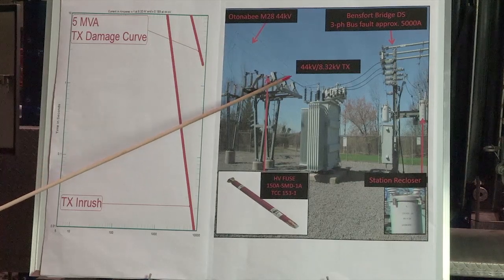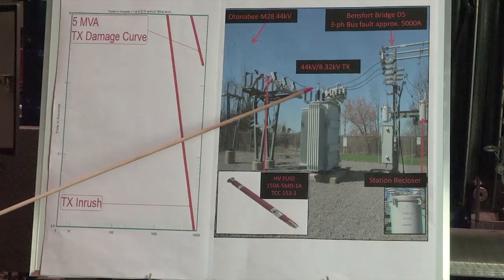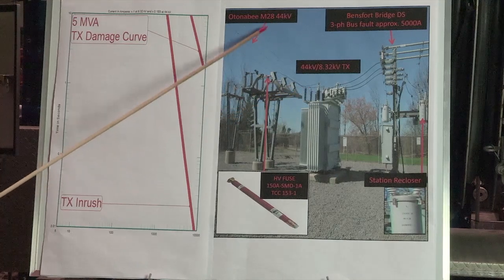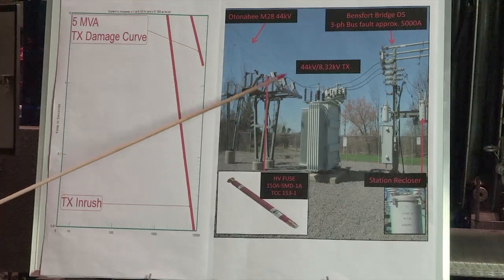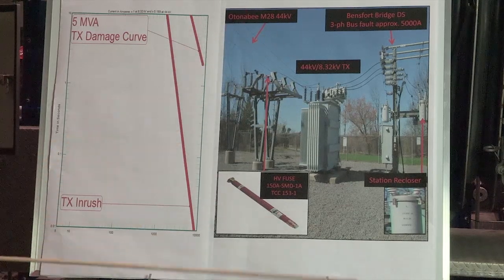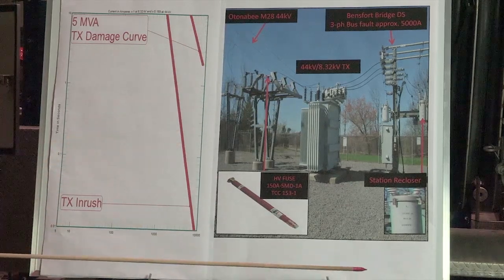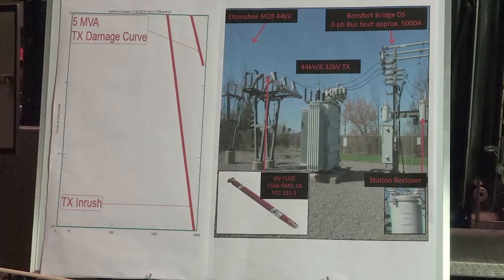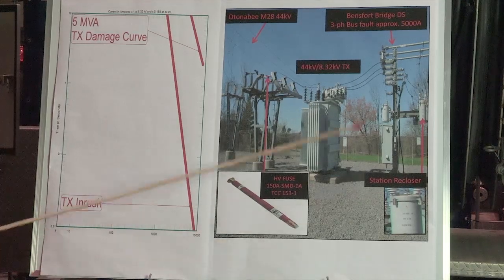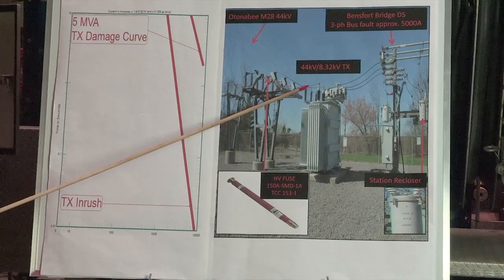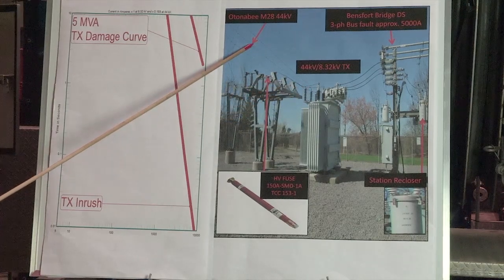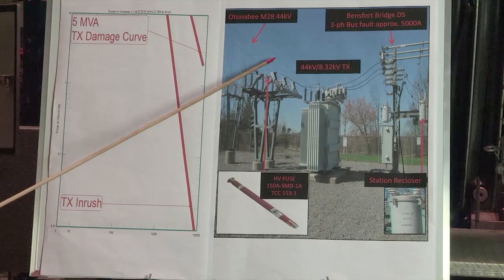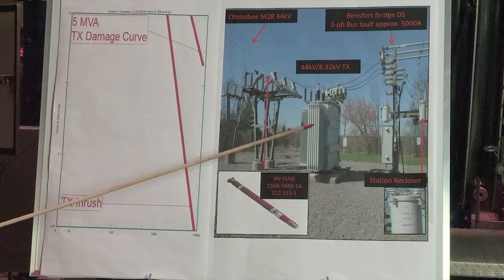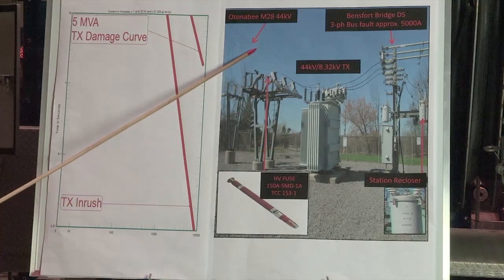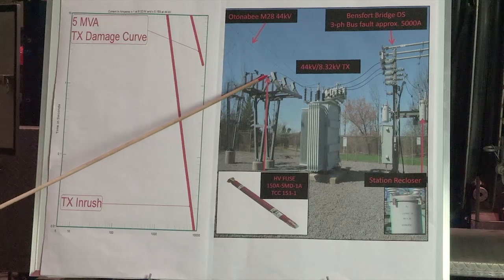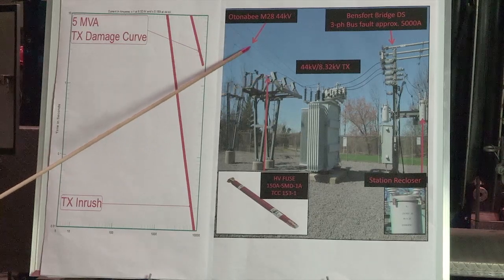Now, at the relay of this M28, we have to make sure that this relay is able to see its whole feeder end faults within less than 1.5 seconds for standard overcurrent protection. After we make our protection studies with the M28 44 kV, we have to coordinate this relay with all the downstream DSs from it. And as far as coordination is concerned, we have to coordinate the high side fuse at the DS with the TS relay.